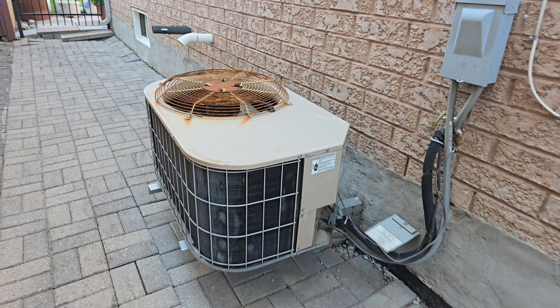This is the reason why they said the air conditioner wasn't working, but it turned out the main reason was that the furnace blower motor wasn't working. So we've replaced the blower motor, and now we're going to turn this on and check how much freon is in this unit.